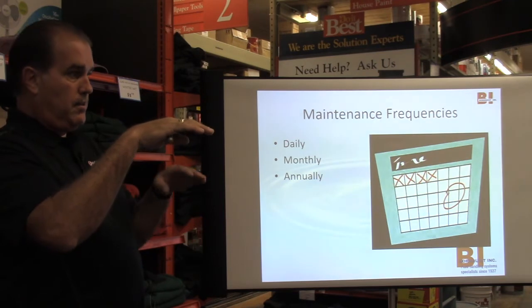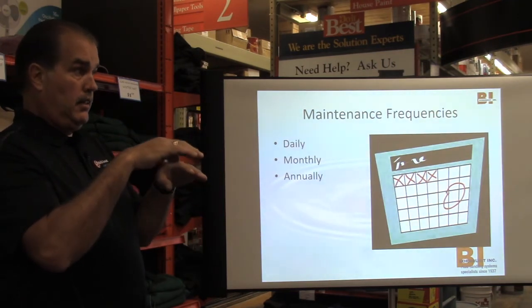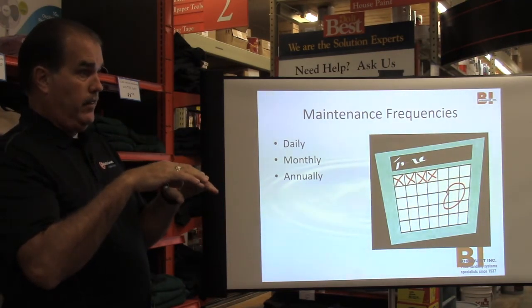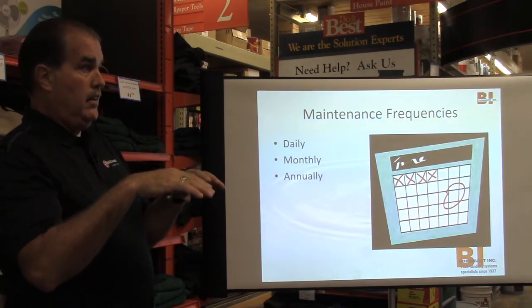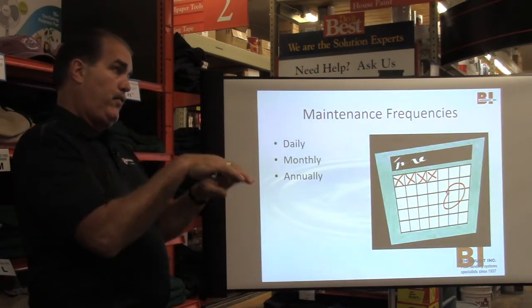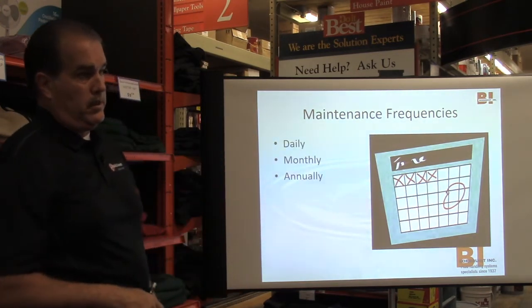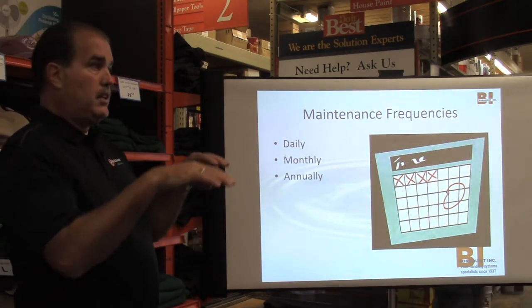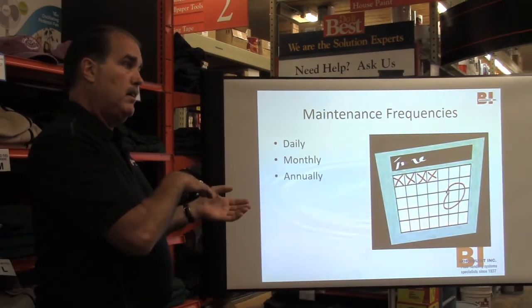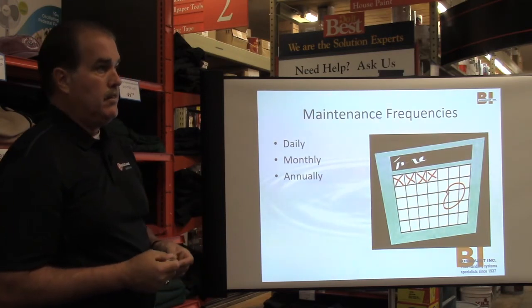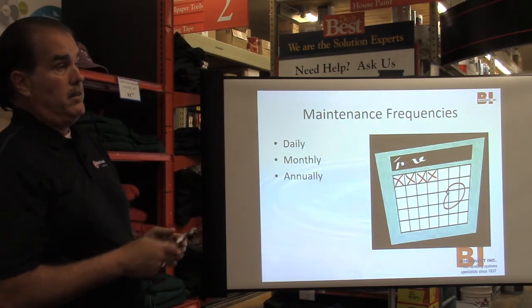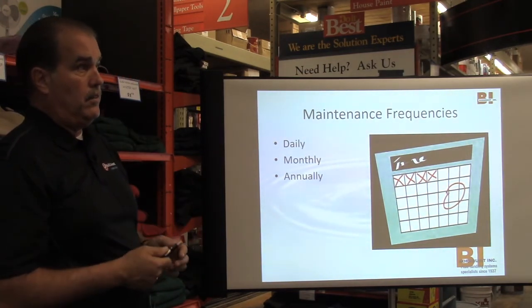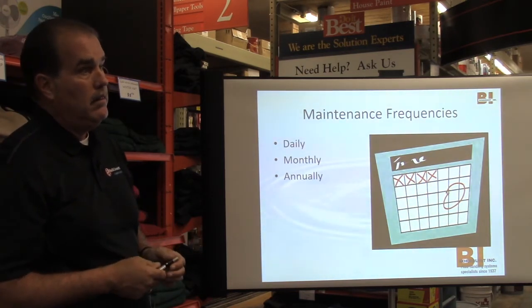So what you do in skimming is turn the boiler on and let it run and let the top of the boiler water flow. The skim pipe is located right at the water line, and that'll skim the crud off the top, which will help stop surging. That's why they do it when they first install a boiler, by the way. It'll skim for 4 or 5 hours to get all that oil out.